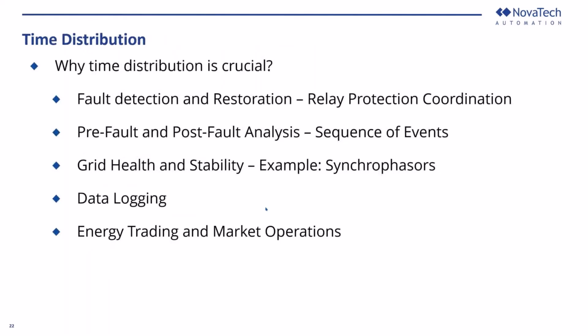Let's take a look at time distribution. Why is time distribution crucial? Well, it's for fault detection and restoration. In case of faults, time sync helps determine the exact sequence of events from the relay. This aids in quickly identifying and root-causing the issue, so that helps in restoring the power system back to stability. With pre-fault and post-fault analysis, if a fault happens in a substation and all the devices are not synced to the same source, then it's hard to find what happened and in what sequence the fault happened. So it's important for all the devices to be time synced. Another application where you would need time sync is grid health and stability.